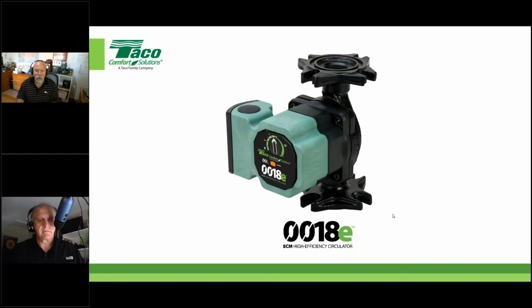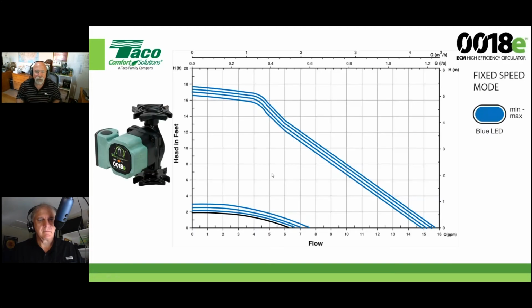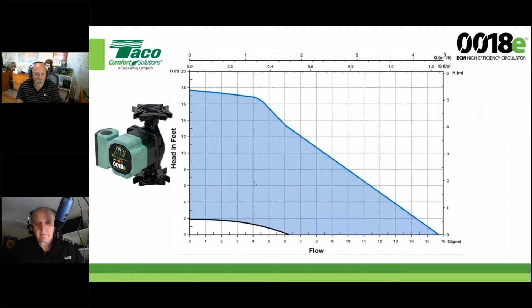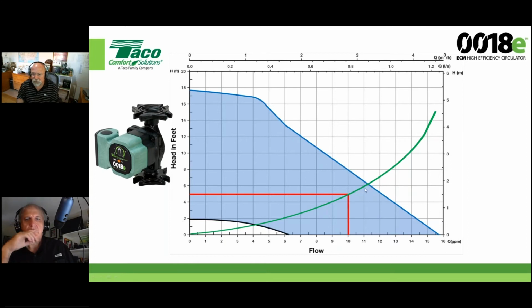Okay, I'm going to throw out my best foot forward right now for this offering, which would be my little 0018E. Remember, with this particular circulator, I have a min-max setting, which means I can go anywhere between the maximum of 44 watts and the minimum of 4 watts. Okay, that's that whole entire shaded area. So our load was 10 gallons a minute. We take it up to 5 feet of head. We cross, and we're assuming that's the actual system curve, the system resistance of the boiler's heat exchanger and near boiler piping, right? And then I come up with an operating point here.